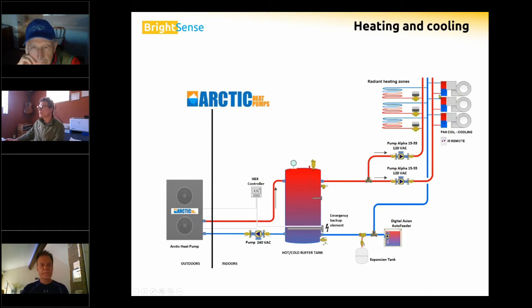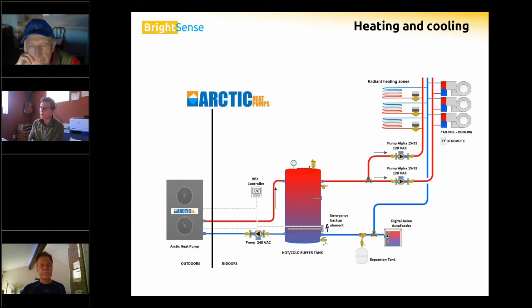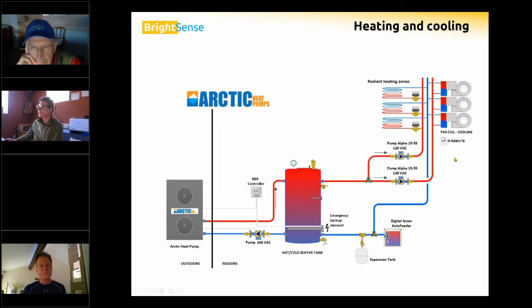This system also shows fan coils for cooling. We could do radiant cooling — if you have an in-slab radiant system, it can be used for cooling — but we need to stay away from the dew point; we don't want condensation on our floors. Fan coils are a simpler way of doing air conditioning, though radiant cooling is very comfortable with no draft or noise.